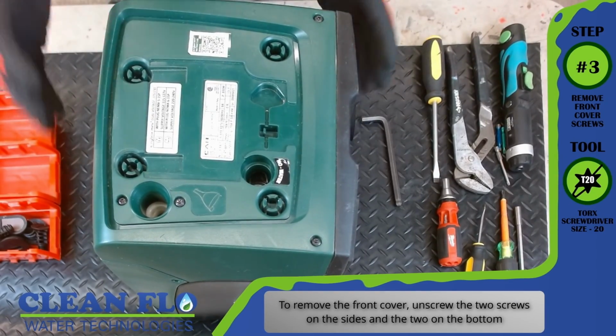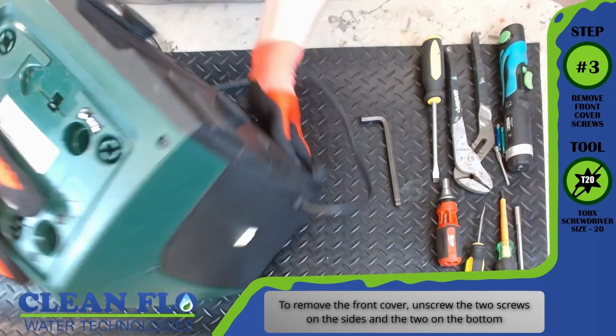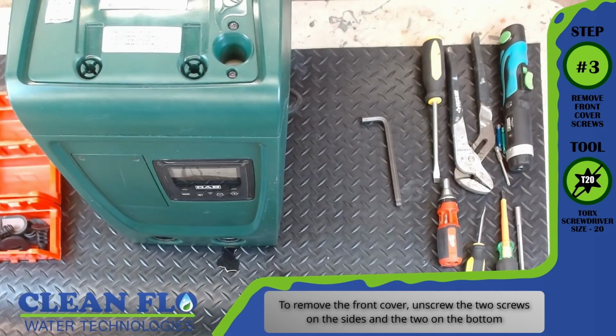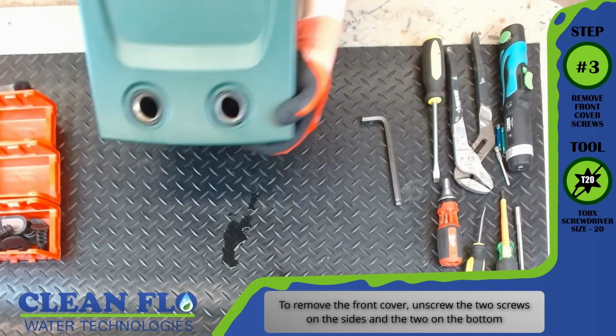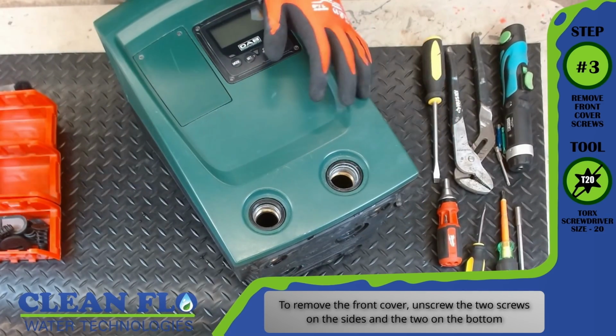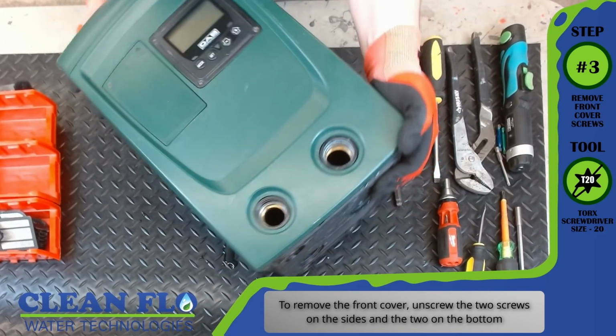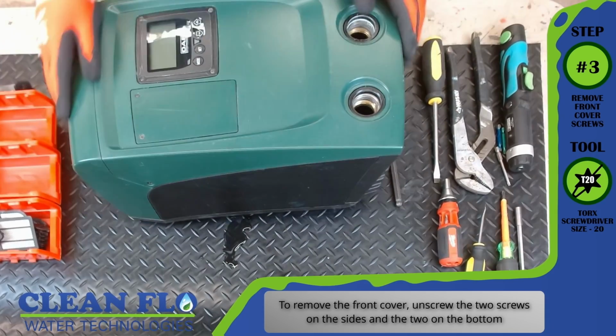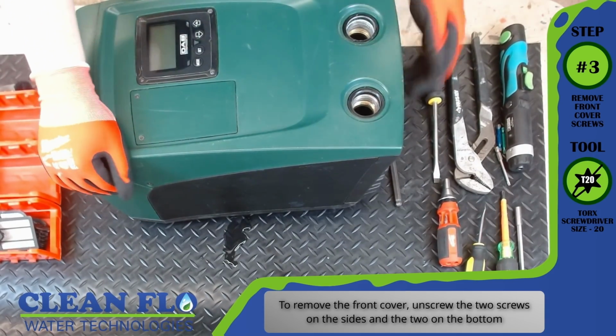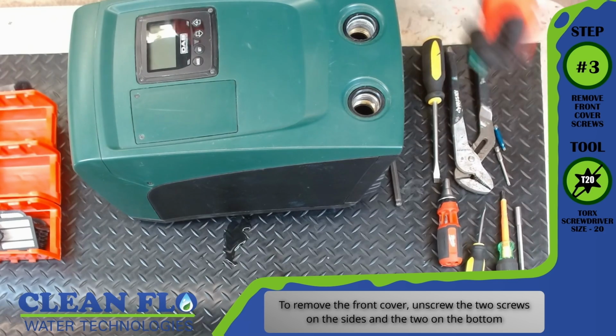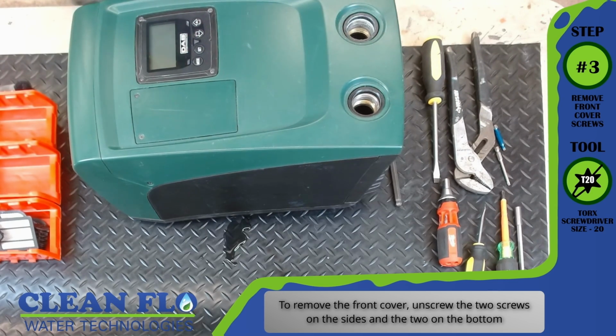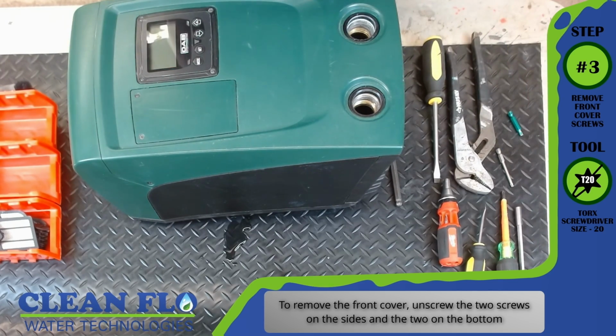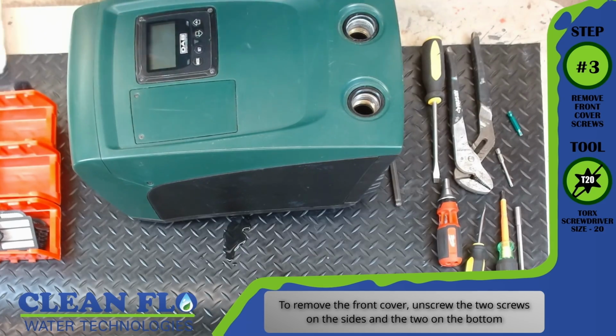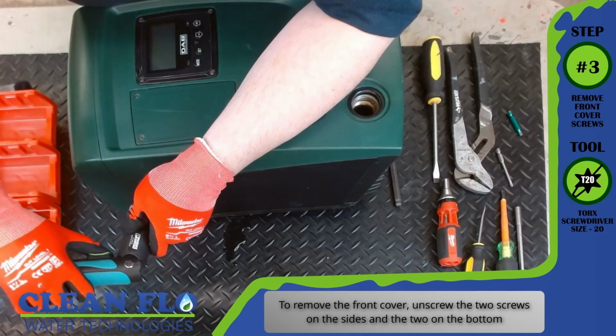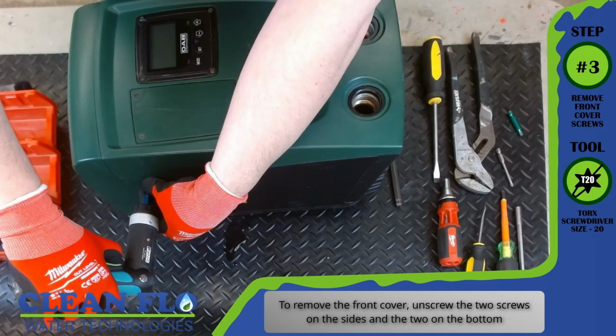Step 3. Remove the front cover screws. Tool, a Torx screwdriver T20. To remove the front cover, unscrew the 2 screws on the side and the 2 on the bottom. The Torx screws can be removed by a hand screwdriver, or if you do have a light-powered screwdriver, not a drill, this is also acceptable. Using a drill will have too much torque and you could strip the screws.